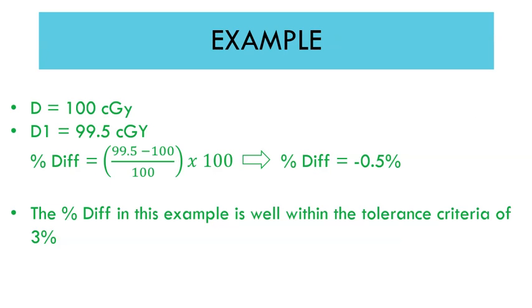Here's an example. Let's say the baseline dose was 100 centigray, and today's dose D1 is 99.5 centigray. Percentage difference using the formula is minus 0.5%. Since the percentage is less than tolerance, this machine is good for the day.